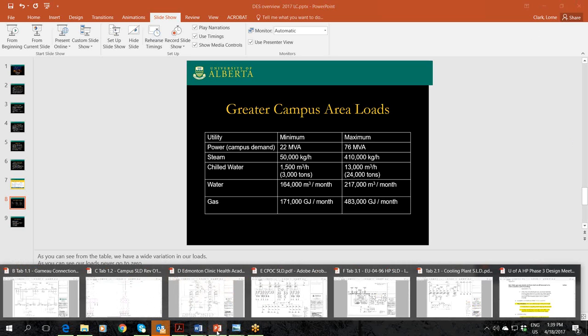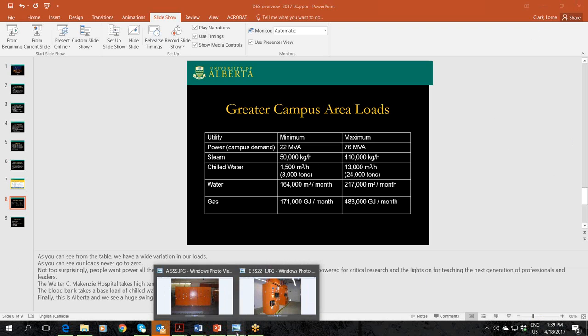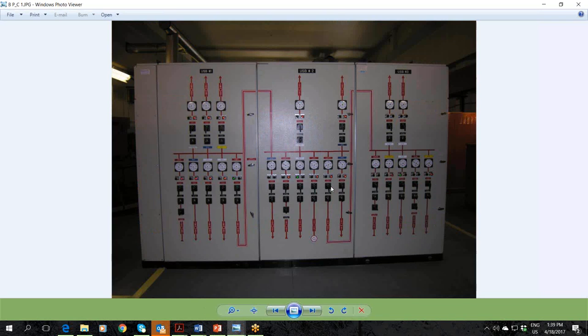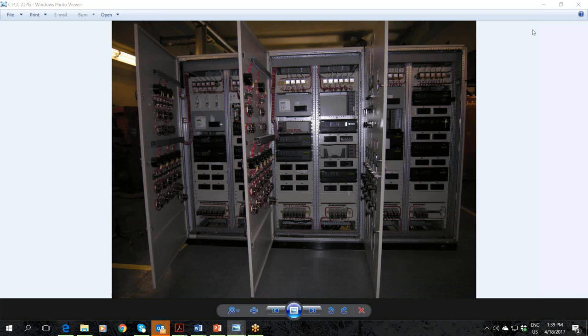Maybe one other thing I haven't mentioned is that on our protection and control, we do have an IEC 61850 communication network set up in certain areas right now. We've got a loop of loops fiber optic infrastructure in place, where we have a backbone and some secondary rings in service. It's basically a long-term project, but certain pieces of it are operating for zone interlocking. For instance, the south switching station has full zone interlocking using IEC 61850, which then reaches over to the cooling plant on campus for zone interlocking as well.